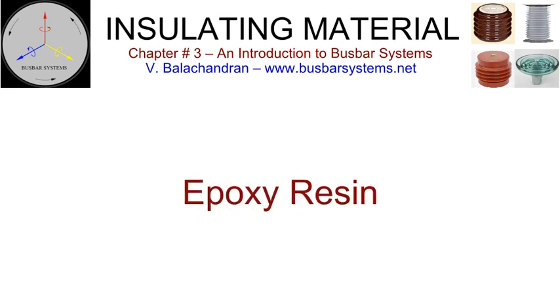Epoxy resin. The process of making an epoxy resin cast component is comparatively simple. Epoxy resin and filler, of correct sieve, are thoroughly mixed in the recommended proportions. The filler is either quartz or alumina. The mix is heated to a slightly elevated temperature and stirred continuously to avoid settling of filler. Hardener and plasticizer are added to the mix in the desired ratio and stirred. Accelerators are added in the right proportion before pouring into the molds. This is an exothermic reaction. The mixing chamber is desired to be kept under vacuum for an optimum mix that is void and moisture-free. The process is also referred to as degassing.